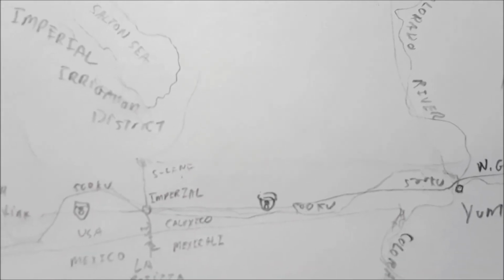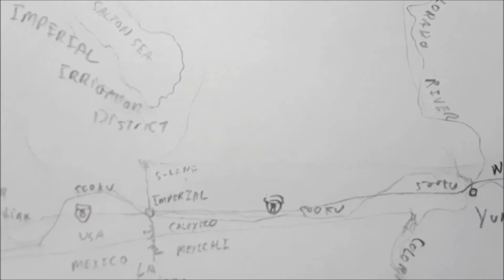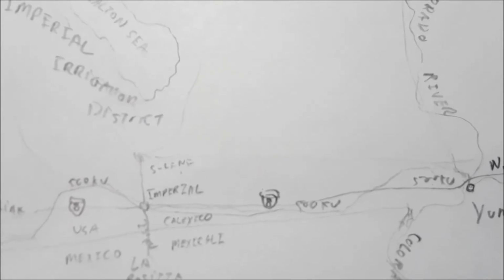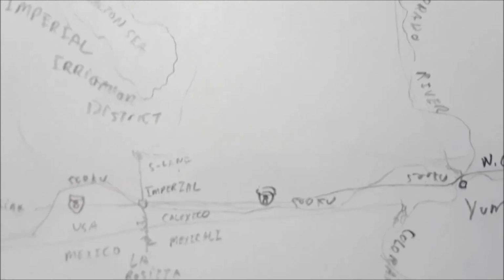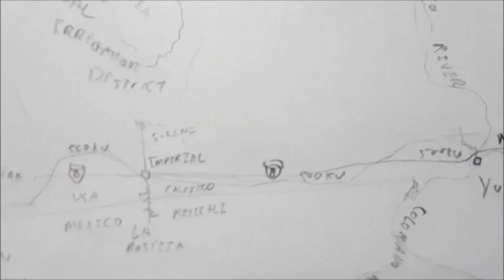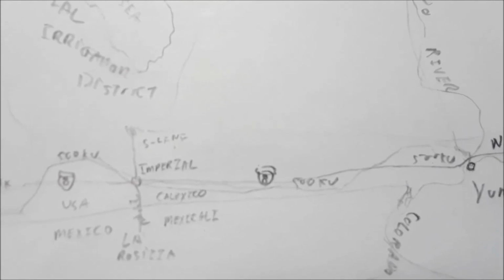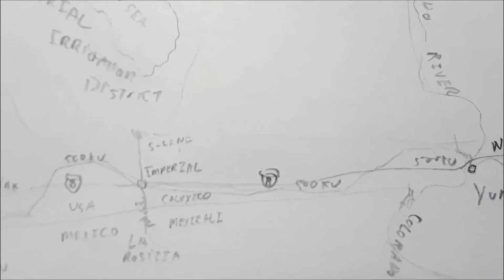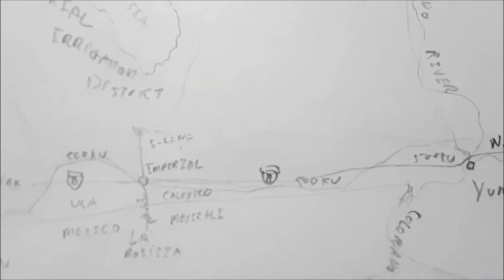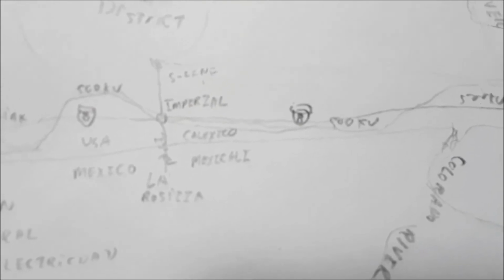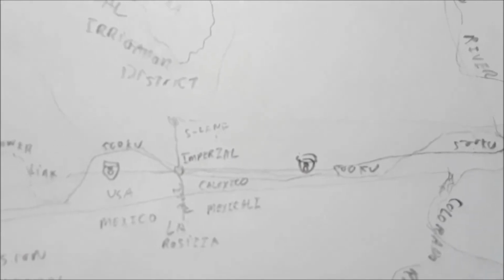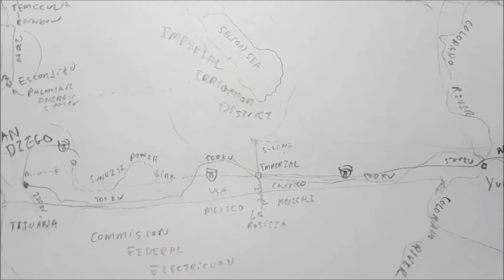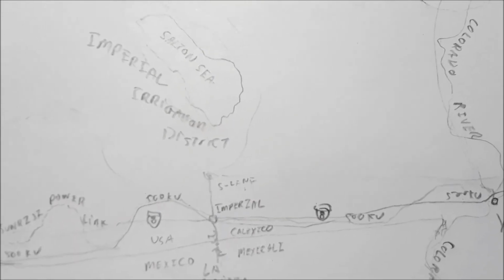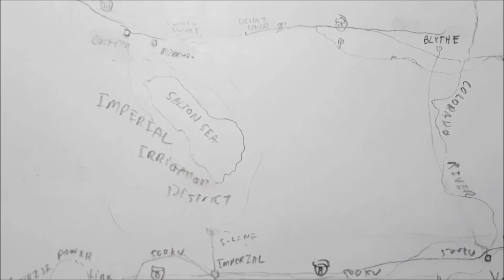The last interconnection to Imperial Valley was a transmission line called the S line that supplied Imperial Valley from the Imperial Valley substation, and that line overloaded as well. However, instead of just tripping that line, the protection scheme initially commanded two generators at La Rosita near Mexicali to go offline. This was to solve a problem that didn't exist and actually made this issue worse. Then the line did trip off, and now Imperial Valley lost power.